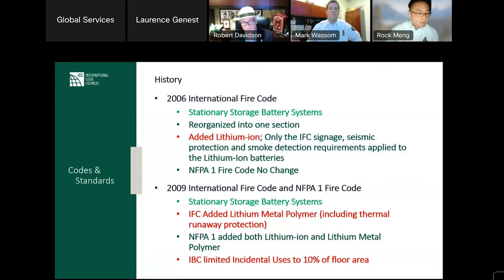And the International Building Code, which is the building code across the United States and many other parts of the world, changed how it treated incidental uses. And for the first time, you had a 10% limit of floor area. Battery installations were always an incidental use, and in older buildings, you'll find a whole floor level of them. But this changed it to limited 10% of floor area, which is actually a major change in the building code that a lot of people don't pick up.